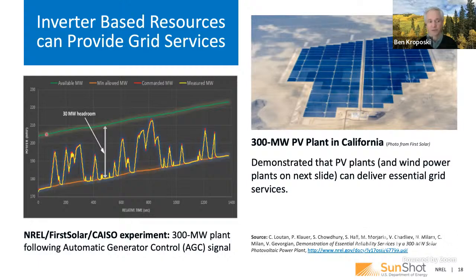In this example, that plant would normally be producing power along this green line. As you can see here, it's running around 200 to 220 megawatts of output power. But what we were able to do is derate that system, or take it off its peak power point, by about 30 megawatts. So we opened up about 30 megawatts of headroom here, and then sent it a signal from the system operator to basically increase power or decrease power. By doing this, it adjusts the system frequency, and it helps maintain the operational reliability services being provided into the grid itself. So what we were able to demonstrate is that these PV inverters can actually be programmed to have very fast response characteristics and follow what we call automatic generator control signals from the system operator.